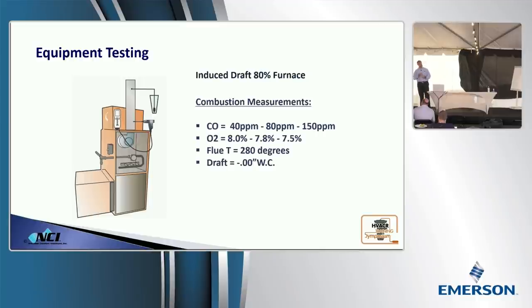Because what that tells us is also, is the gas valve seated? So if you see a rise in CO after the equipment shuts off, the gas valve's leaking more than that 10% of lower explosive limits. You're actually seeing the raw fuel leak past the seats of the gas valve, converting to carbon monoxide as it comes into contact with that hot metal. What I have seen 100% of the time that I've seen rising CO on shutdown is that the gas line was done incorrectly. There was no sediment trap, no dirt leg. All that trash that's in the line is getting through the screen and into the valve and warping the seats.